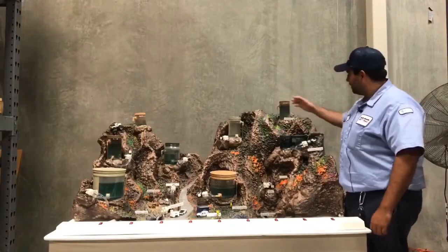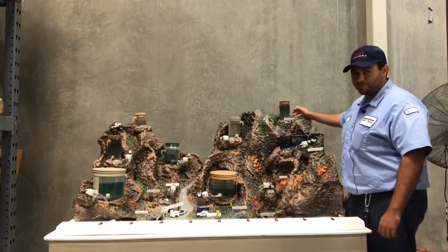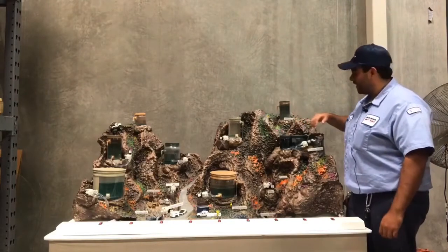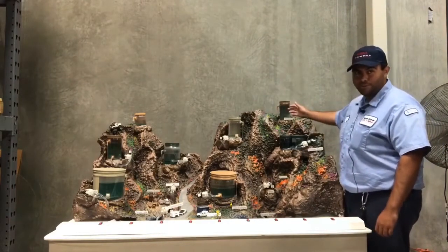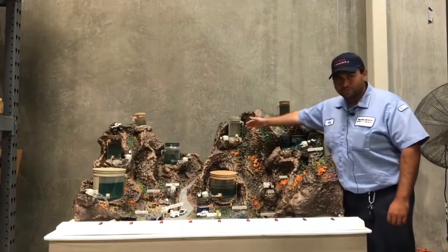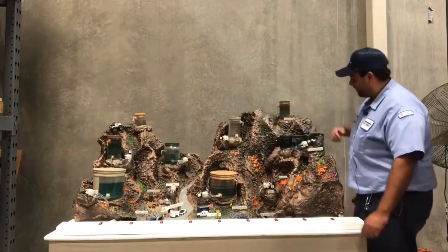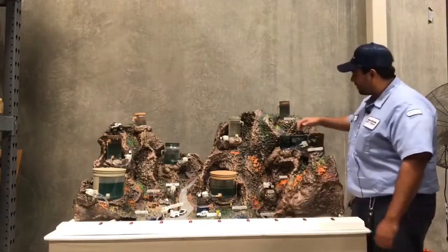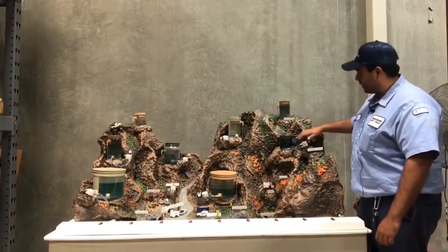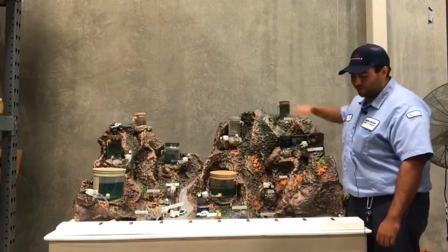If I continue to overflow the tank, or that booster is pulling from a different tank and I'm not taking care of the levels on the other tank, I could either overflow the one that it's pumping up to, or I could drain the one that it's pulling the water from. To stop that from happening, you have to monitor all the other tanks as well and make sure they have adequate water to move it all the way up.